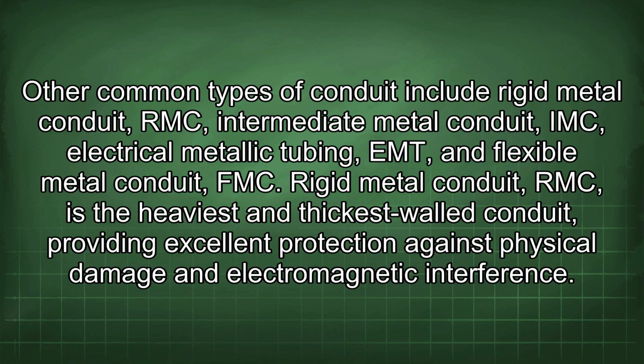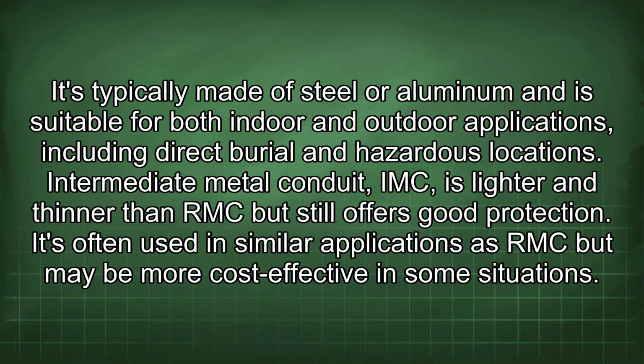metal conduit (FMC). Rigid metal conduit (RMC) is the heaviest and thickest walled conduit, providing excellent protection against physical damage and electromagnetic interference. It's typically made of steel or aluminum and is suitable for both indoor and outdoor applications, including direct burial and hazardous locations. Intermediate metal conduit (IMC) is lighter and thinner than RMC but still offers good protection. It's often used in similar applications as RMC but may be more cost-effective in some situations.